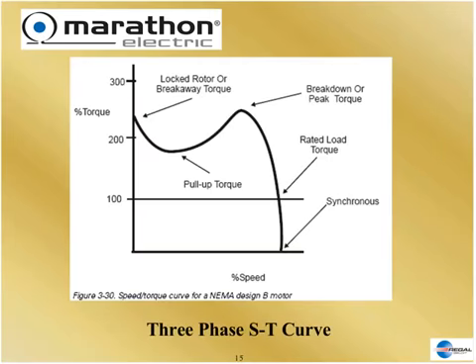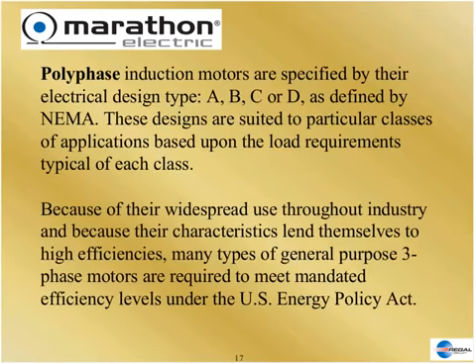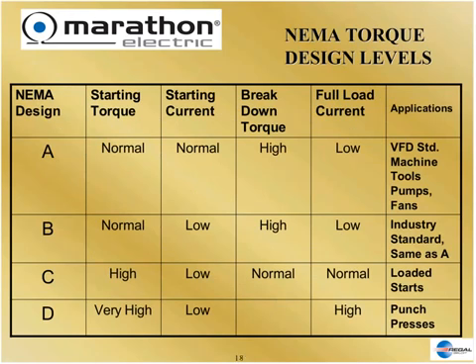The shape of the curve changes depending on whether we have Design A, B, C, or D. They're widespread through the industry, and efficiencies are usually mandated, unlike single-phase motors. The absolute standard is Design B — those are general-purpose motors found in most applications. A, C, and D are special; they differ because of the shape of their speed-torque curve profiles and the machines that use them.